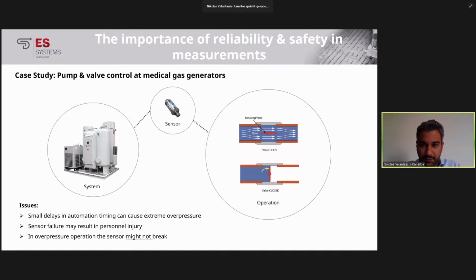So it's really, again, very important, in order to have reliable and safe measurements, to pick the correct sensors that can tolerate this overpressure and avoid personnel injury due to the burst of the pressure, or having incorrect information from the pressure measurement due to the damage of the sensors. It is important to note that in this case, the pressure sensor will probably not break.